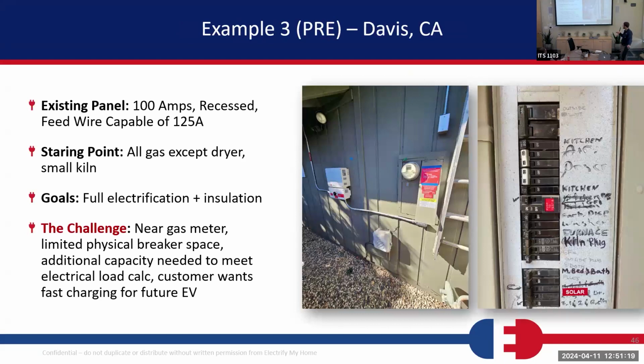Okay, this one's in Davis, underground feed from the utility. We learned a lesson on this one. The feed wire was capable of 125 amps, so we saw that and said, oh wow, this wire is big enough from the utility, we can just put in a 125 amp panel. And then when we went to roll that through the process, PG&E made us aware that there was direct burial, so it wasn't conduit. And so all throughout this whole neighborhood, we're still stuck at 100 amps. So we had to figure out another way to make this work.